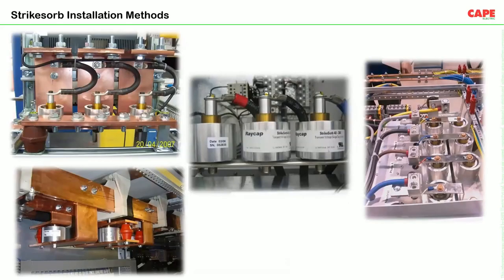These are the various connection examples of bus bar mounted SPDs, how they are connected. Normally, you can make a separate earth bus bar for connection of these SPDs, and also you can connect it on the phase bus bar. With this type of connection, since it is connected on the bus bar, wire length is zero, very, very short. Only a small wire length of, let's say, 10 mm is required just to connect the SPD with the body of the panel, which is again connected to earth. So with the use of this kind of SPDs, we can make wire length very minimum, almost like zero.